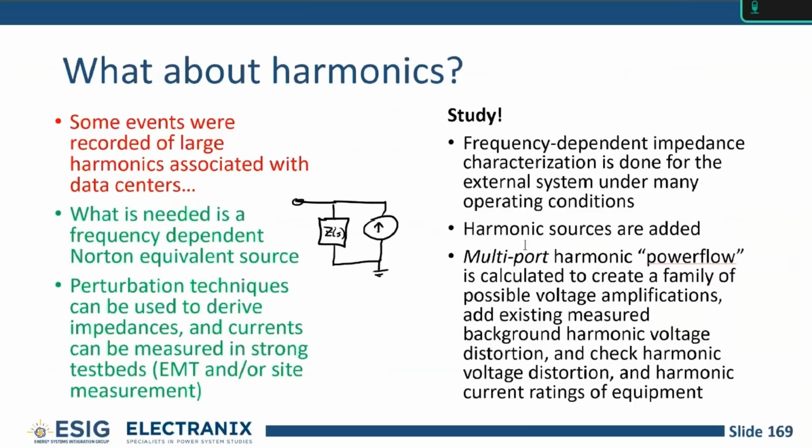There have been events recorded of large harmonics associated with data centers. So this isn't something we can ignore. It's probably a real problem in some cases. But the interesting thing about this, from the harmonic studies we've been a part of, is that at least for one, we've done only a couple, for one of these very large loads where we had good data, we had good harmonic models, the load itself in this case was not a significant source of problematic harmonics.